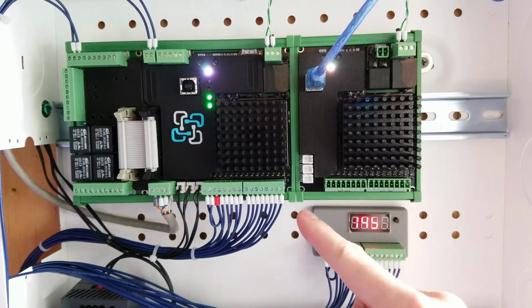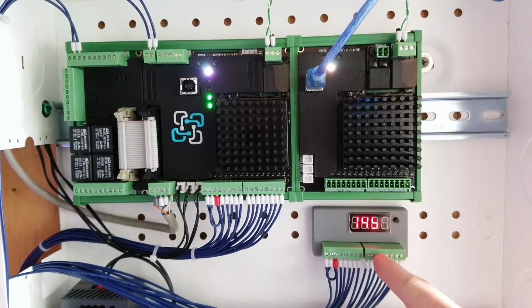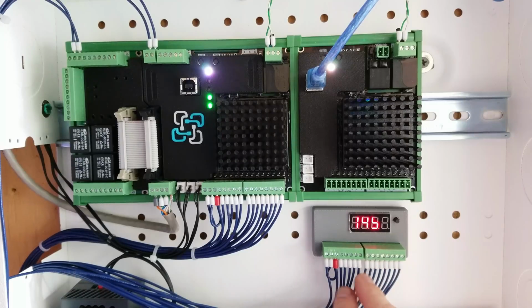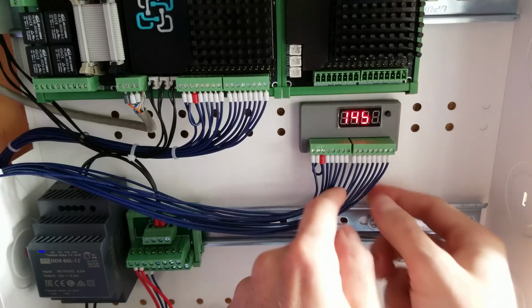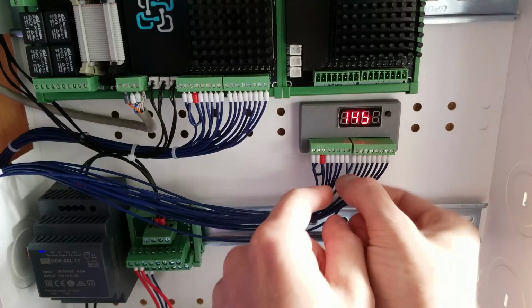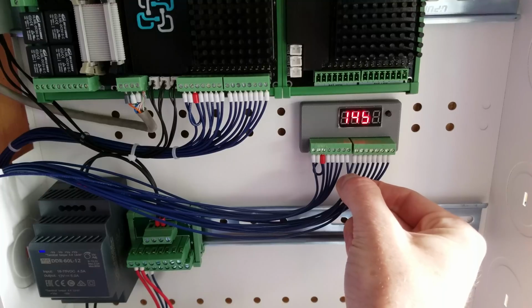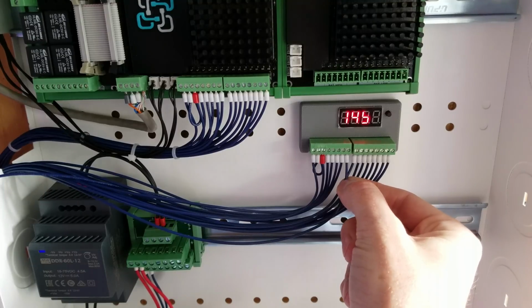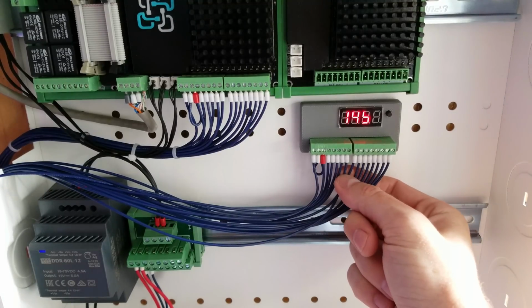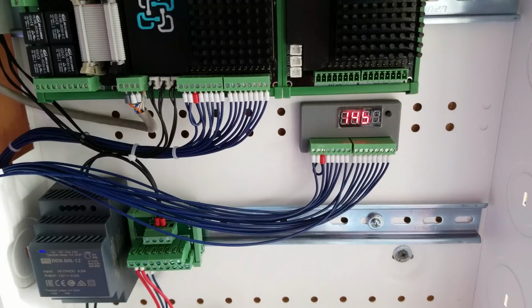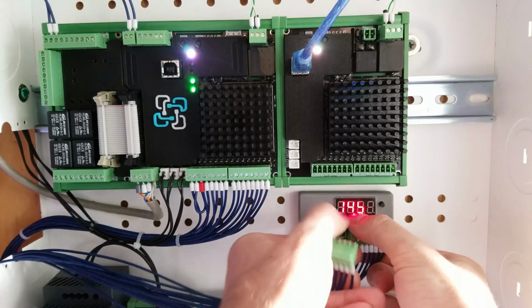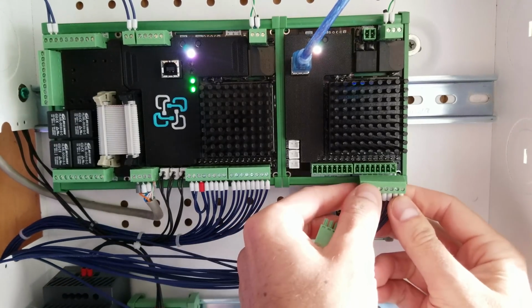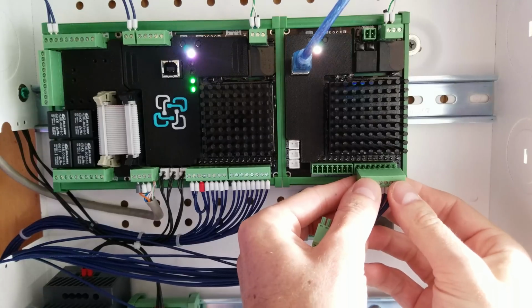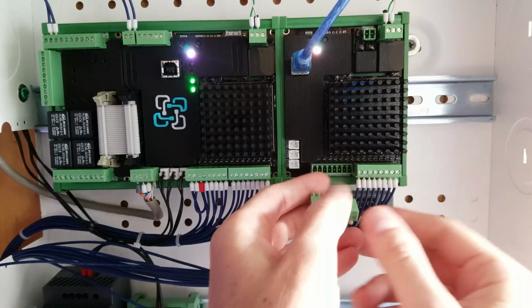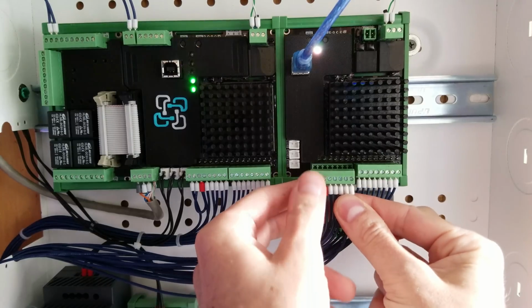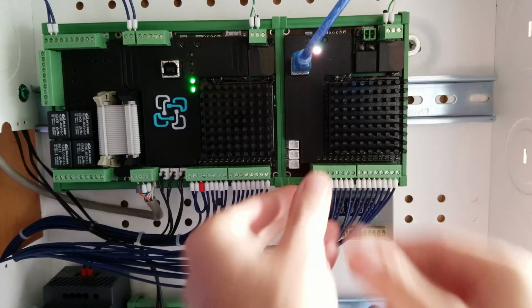It still says pass. So I'm ready to remove these two connectors and place them in the MM8. As with the Watchmon 5, you'll always want to do the lower voltage connection first and make sure you don't mix up these two connections. A good way to avoid mixing these up is to take pins 7 and 8 and just put a zip tie around them. That way you cannot mix them up. I'm not going to do that in this particular video, but I definitely recommend doing that if you're doing a similar installation. So remove both of them. So lower voltage first, line up the pins, and then you'll want to press it in a quick motion. Higher voltage, line up the pins, and press it in.